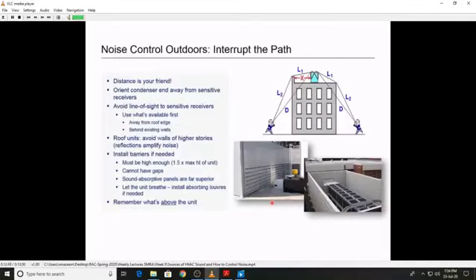It's very valuable to be able to interrupt the path of sound outdoors. Remember, distance is your friend. If you're putting in something like a large rooftop unit, orient the condenser end away from sensitive receivers. Use the physical structure to block that sound. Avoid using line of sight to sensitive receivers. Use what's available to you. Mount your units so that they'll be blocked by the roof from line of sight, instead of locating them toward the edge of the roof where the receivers on that side will have line of sight and get more noise.